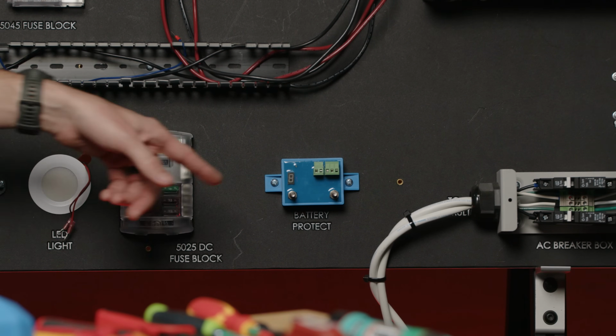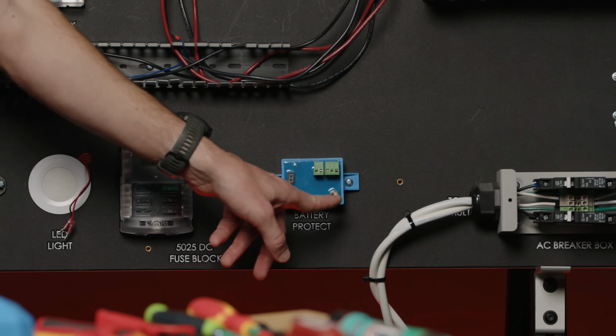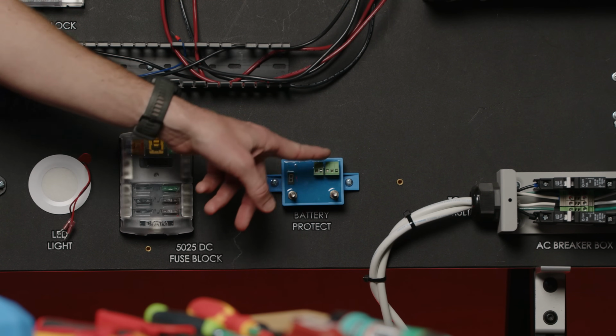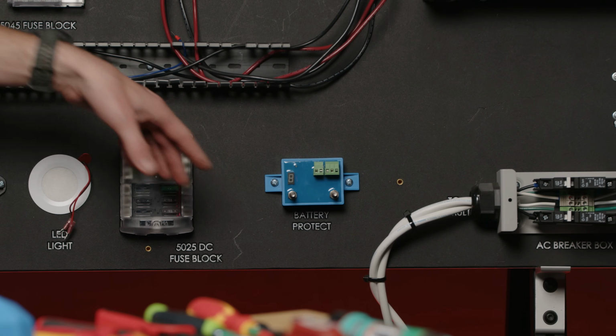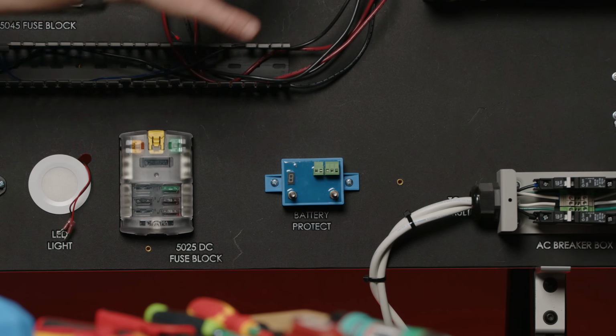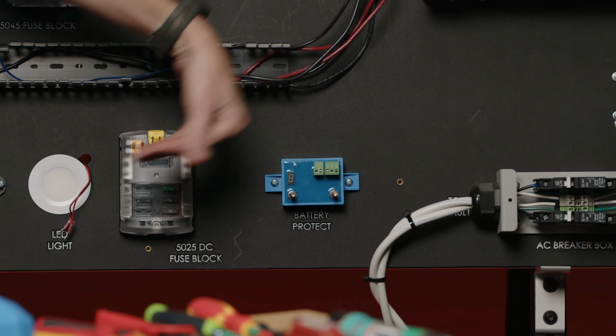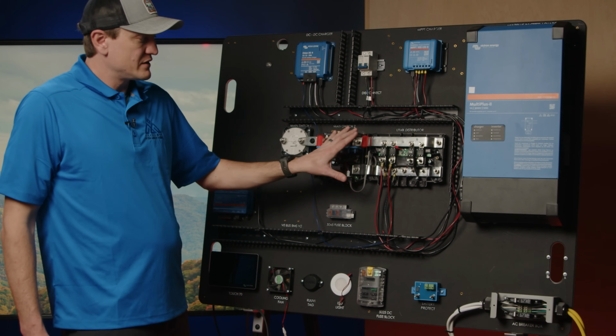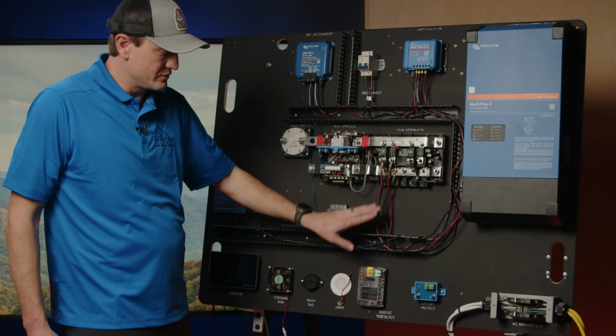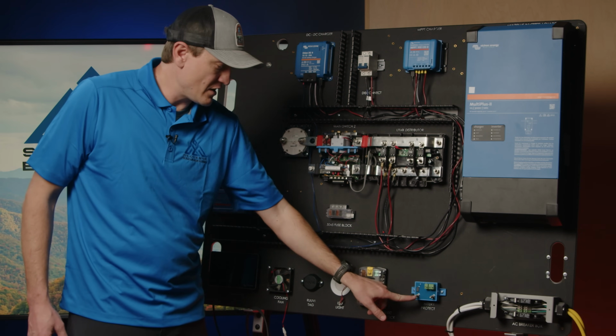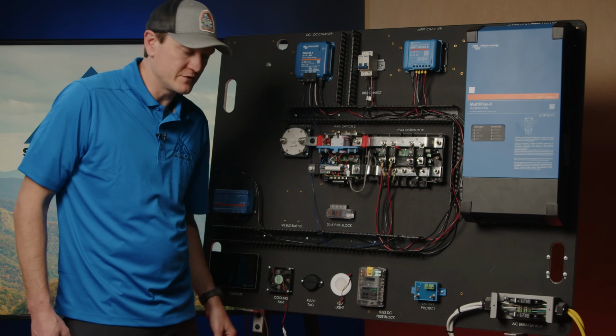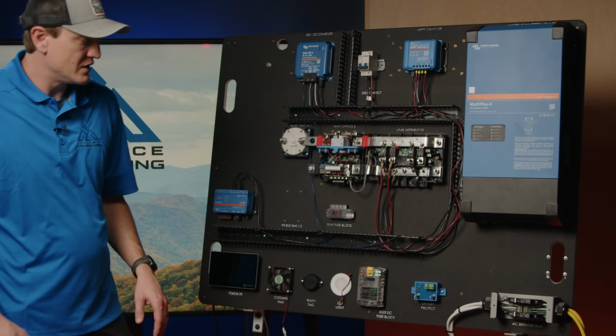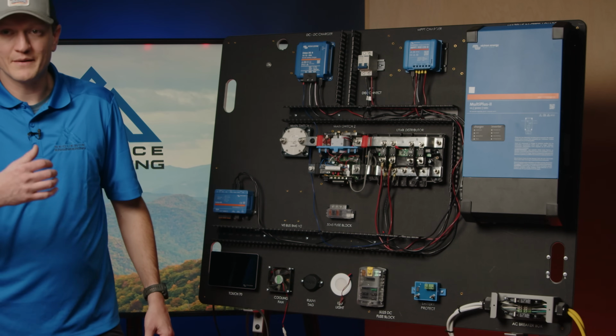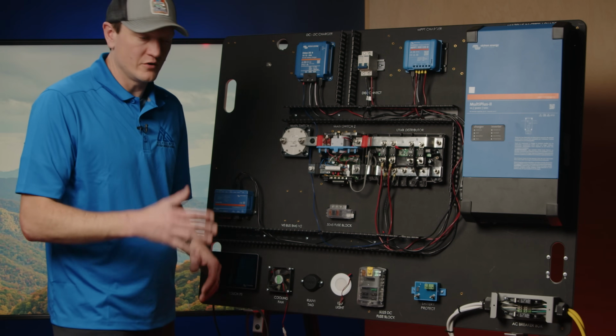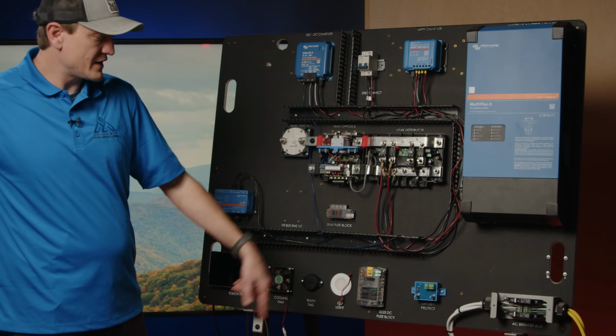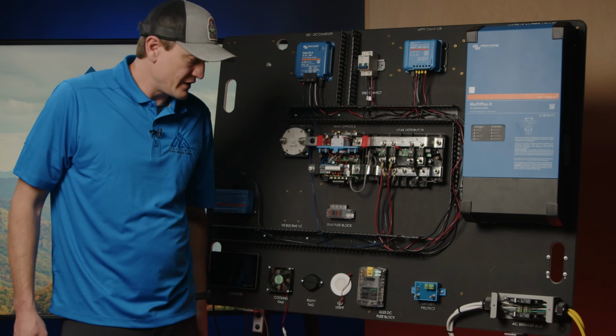With that being said, you also need to note that it has an in and an out. So this terminal over here is in, this terminal over here is out. It is clearly labeled on the face of the unit. You need to position this device in your system such that the current is going to flow in one direction. Now, here we are expecting the current to go from Lynx Distributor down the wire to the in terminal over to the out to our DC loads downstream. Okay, so be sure that you position that device correctly. If it's being used on a charger or in some other application, you may have to flip the in and the out based on the current flow. Okay, so we're going to go ahead and we're going to get that guy wired up and show you ultimately how it all comes together.